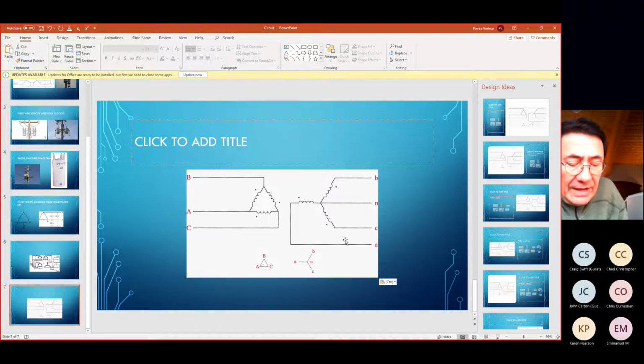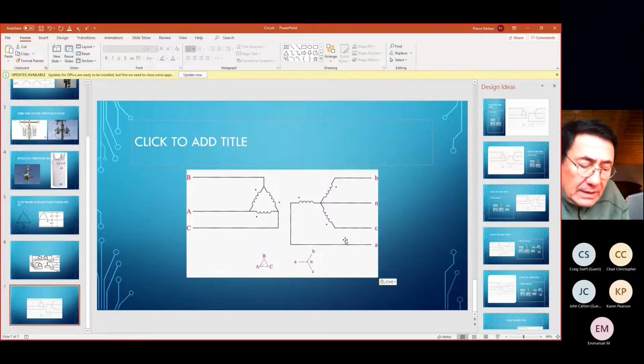If that voltage waveform has a greater area under the curve, which would occur with multiple spikes, therefore adding the area under the curve of all the spikes, or what is no longer a spike but now a surge, the metal oxide varistor will receive too much energy across its resistance and it will fail. It will fail catastrophically and hopefully will blow open, at which point it won't damage anything in the drive. But if there is a short circuit failure, and that's unpredictable, it's kind of a roll of the dice, you could have some issues, obviously. Normally they'll fail open because the little spindly legs on the metal oxide varistor will melt, as would, say, a fuse.